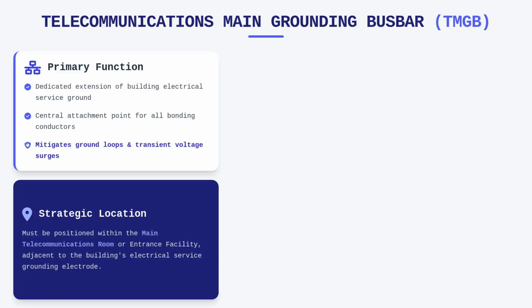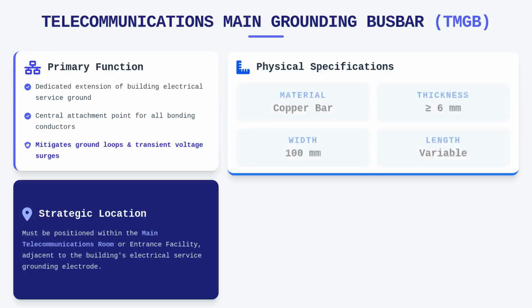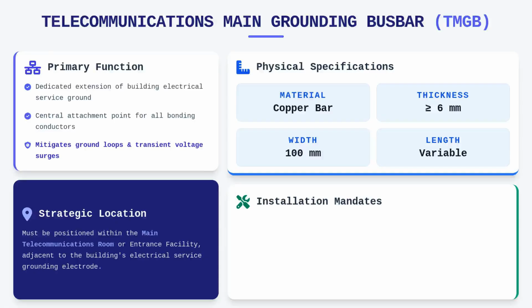You must position the TMGB within the main telecommunications room or entrance facility, situated near the building's electrical service grounding electrode. The bus bar itself is typically a pre-drilled copper bar with a thickness of at least 6 millimeters and a width of 100 millimeters, though length varies based on the number of required connections. When installing this component, you are required to use appropriate insulators to isolate the bar from the supporting structure unless the design specifically calls for otherwise.